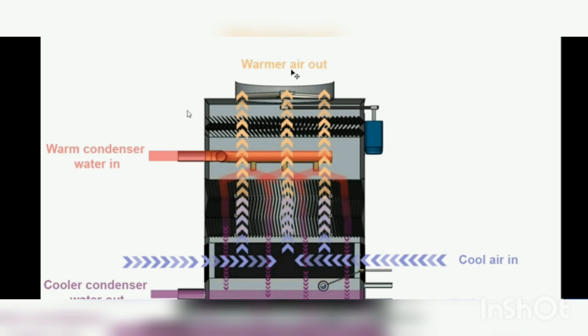The warm water goes inside the cooling tower and is sprayed with the help of spray nozzles onto the packing, also known as fill. In the fill, ambient cooling air comes in contact with the warm water, and because of the temperature difference, heat transfer takes place. After the heat transfer, the cooling air becomes warm and exits via the fan at the top. The cooled water is then collected at the bottom basin.